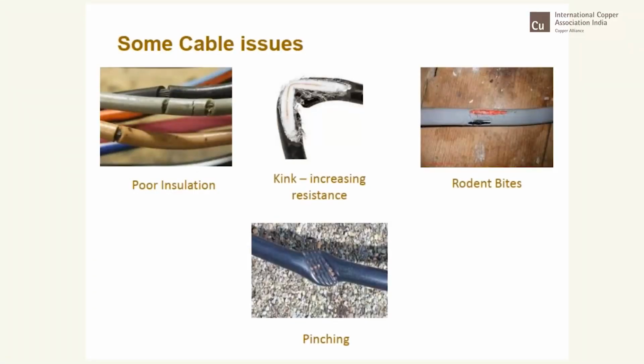I mean, suppose the current flows. If it gets heated, it should be able to withstand that heat and all that. So then kink: during installation we do certain things without being aware of the impact on the cable, because we don't physically see any damage. So we bend it the way we want. That can cause tremendous stress in the metal, and then it could be a source of high resistance and temperature generation. Rodent bites, as we were mentioning, and then pinching: you use some tool or some such thing which pinches, and then you have the insulation getting damaged.